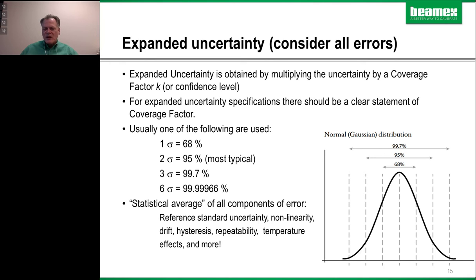So remember, on the previous slide, we were just talking about accuracy, but there's so much more. You know, how accurate was the reference standard that was used to help state that accuracy? That needs to have that 4-to-1 or 10-to-1 ratio. And then these other components get averaged in, if you will. And there's more than just this. So when you hear somebody state uncertainty, that gives you a much higher level of confidence in how valid the instrument is in making a measurement.